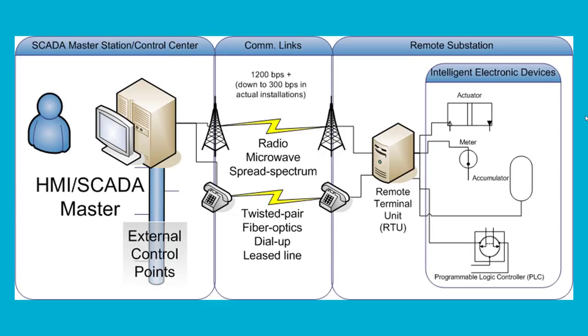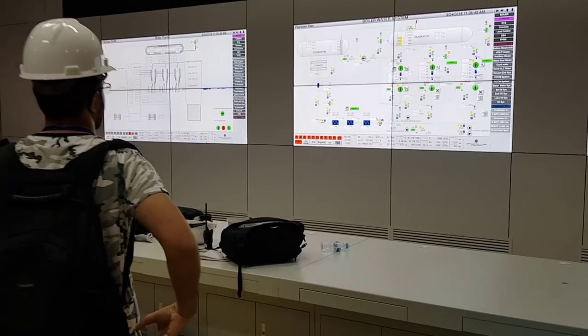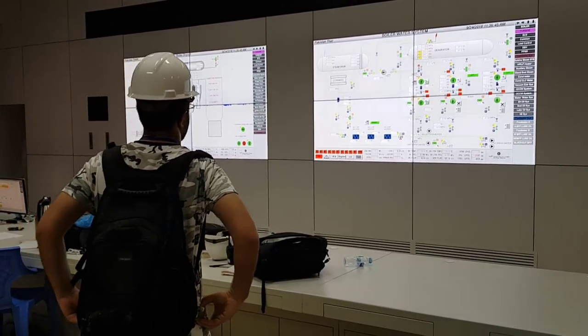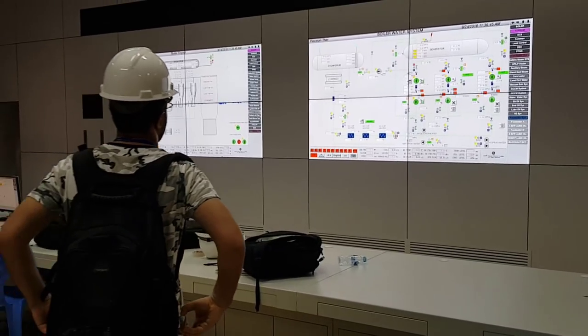Now if you have RTU, it needs to have some communication network to send the data to the master control room. For that, either you are using a radio microwave system, or you are using twisted pair fiber optics, and there might be other options also. The whole purpose of RTU is to gather data from field devices — which can be actuators, valves, electrical machines, PLCs — and then RTU shares that data via communication network to the master control room, where you have HMIs and different operator screens to visualize and control that information.